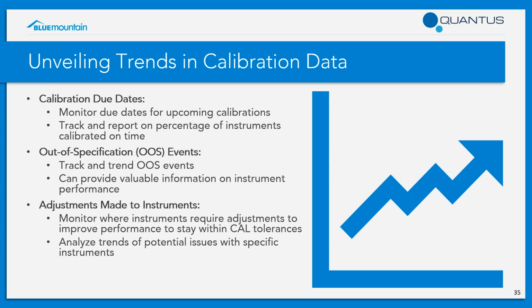Of course, calibration due dates and compliance. As you're doing your work throughout the month, you want to make sure that we're monitoring these for upcoming calibrations to ensure that instruments are calibrated within their defined service intervals. And you want to track and report on the percentage of completed items that are calibrated on time to make sure that your vendors and your in-house personnel are staying up to date with their services.